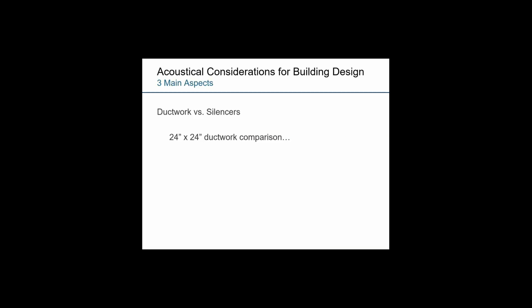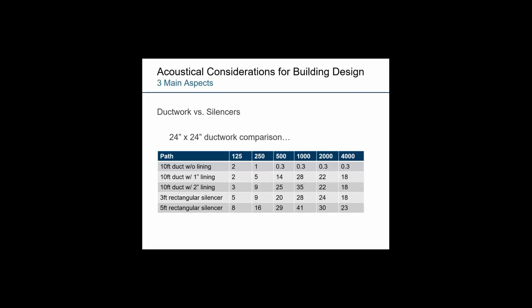We often look at things like ductwork and silencers or sound attenuators as well. And looking at a comparison of the absorption or attenuation potential, this table is kind of interesting to see the differences on where sound can be absorbed and attenuated using different elements. And this is taken from some references through ASHRAE and through manufacturers' handbooks. But in general, looking at ductwork, a 24-inch by 24-inch piece of ductwork, 10-foot long without any lining, would have minimal sound absorption or attenuation or insertion loss. So very little reduction in sound by having unlined ductwork.